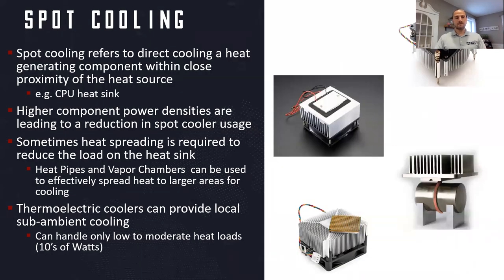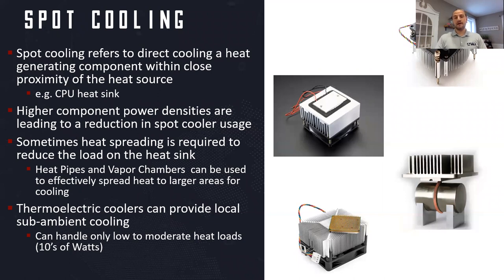First we'll talk about spot cooling, which refers to the direct cooling of a heat generating component within the immediate proximity. You're seeing on the right here a number of examples — mostly CPU coolers and some thermoelectric-based devices. Components that are coming out today tend to be high enough power where there's not enough space immediately available around the heat generating component to get enough heat sink volume to dissipate the energy at an appropriate temperature. Many of these applications shown are relatively low power where a heat sink fits within the footprint of the heat generating component itself.